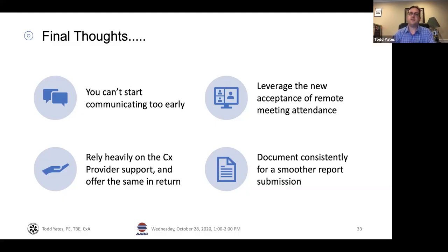As I said, if you have different technicians and you're reporting the same issue or making a note of the same final settings, use the same verbiage and same terminology to do it. If you use one phrase for the first 3 air handlers and a different phrase on the next 2 air handlers, a designer is going to pick up on that inconsistency. If you're looking at them individually, it looks fine, but when you put it together in a report, that inconsistency raises questions. If you label equipment the way you normally label that type of equipment, and it's different than what's on the drawings, that again, it's another stumbling block.